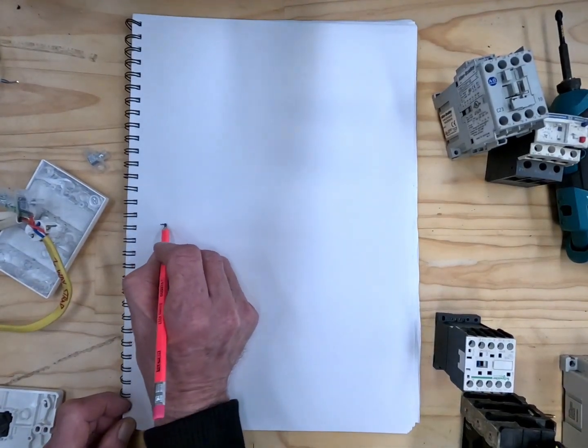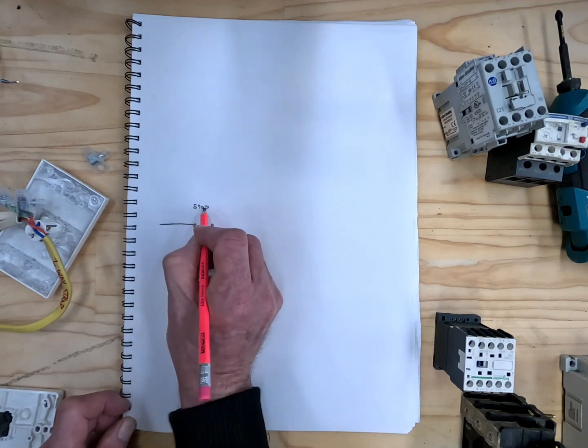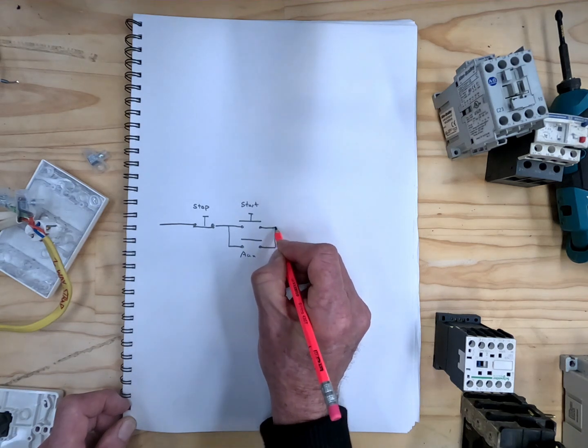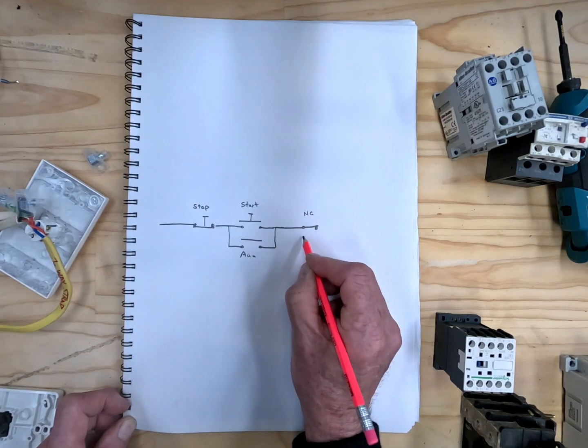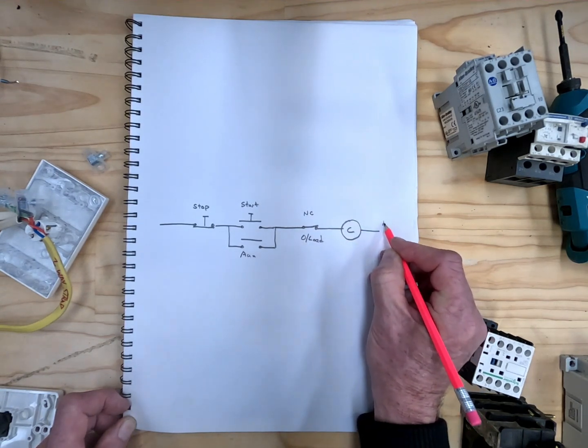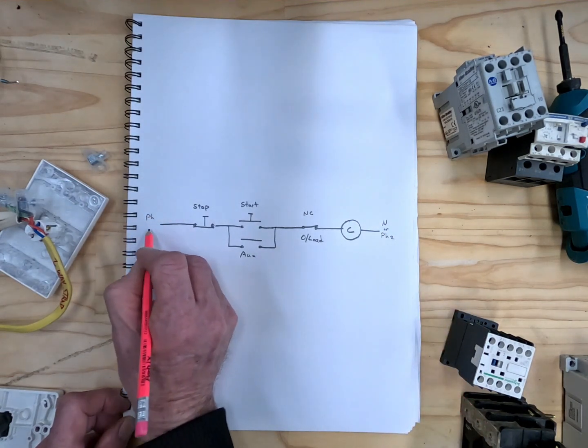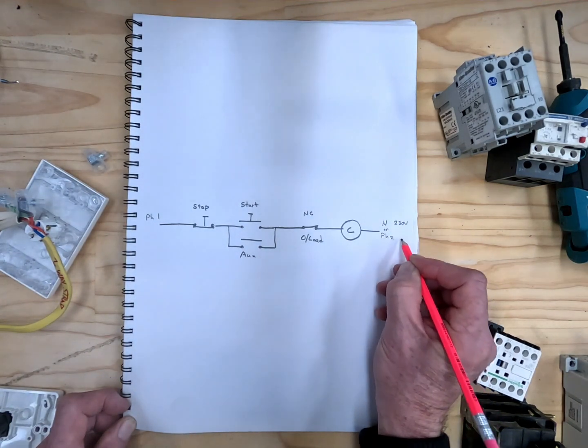Here we're drawing a stop/start station for a contactor. The auxiliary contact of your contactor, also called your hold-in contact, is the normally open contact. The overload wires onto the coil of your contactor — that can be either a neutral or maybe a phase, depending on whether it's a 400 volt or a 230 volt coil.